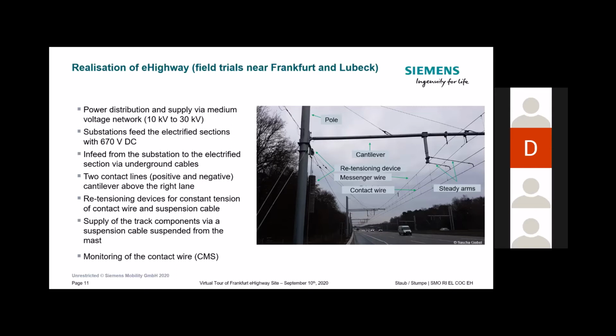It basically detects the tensioning force inside the wires, inside the contact wire and the messenger wire. And if it detects any change in force of the tension conductors, which could be due to the unlikely case of a break of the contact wire, or a tree falling on it, or anything else, this causes a change in the measured tensioning force. This change is detected, and then we know something is wrong, and it automatically switches off the electricity from the wire.